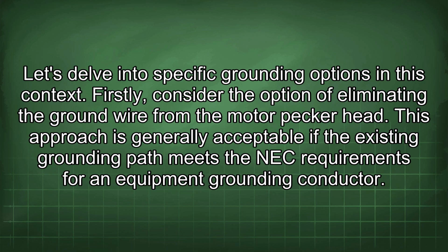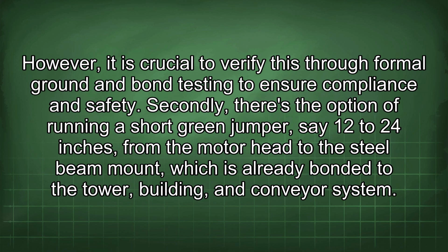Firstly, consider the option of eliminating the ground wire from the motor pecker head. This approach is generally acceptable if the existing grounding path meets the NEC requirements for an equipment grounding conductor. However, it is crucial to verify this through formal ground and bond testing to ensure compliance and safety.